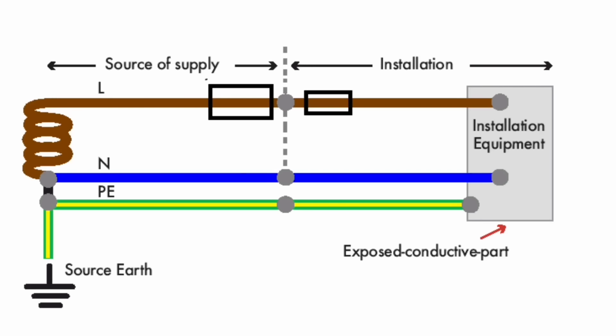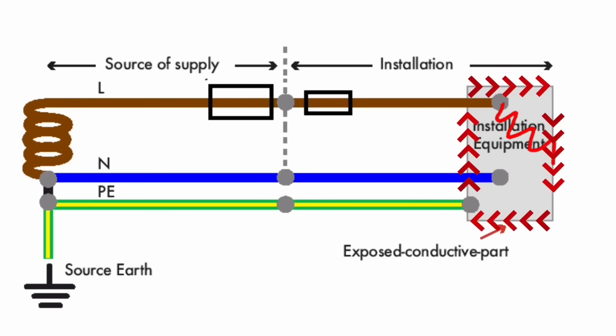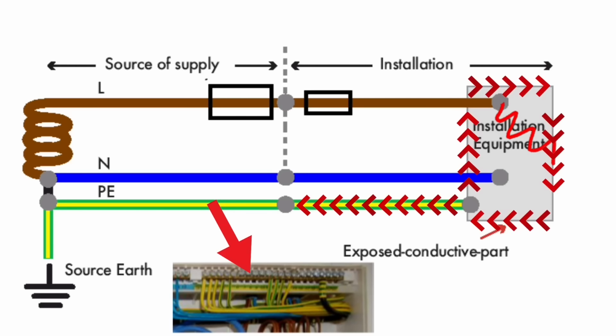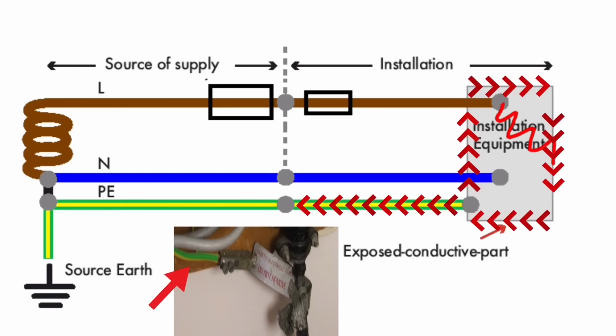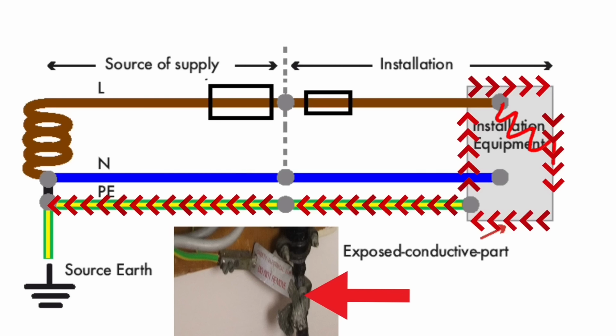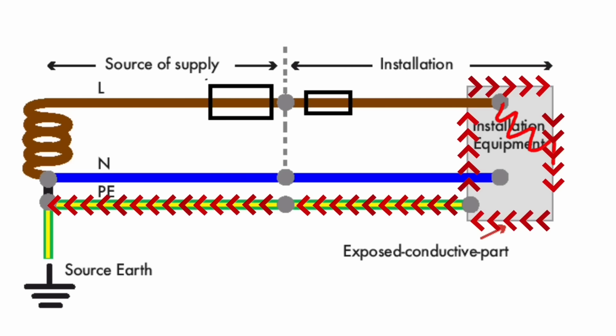The earth fault loop impedance path of an installation connected to a TNS earthing arrangement. In the event of there being a fault between the line conductor in the installation and an exposed conductive part, the fault path or earth fault path would be as follows. The exposed conductive part would become live. This is connected to the circuit protective conductor, the CPC. This would become live. This goes back to the earth terminal situated within the consumer's unit, which would become live. This is connected to the incoming earthing conductor, which comes in with the double insulated meter tails. This earthing conductor becomes live. The earthing conductor is connected to the lead or steel sheath of the supply authority's cable, which becomes live.